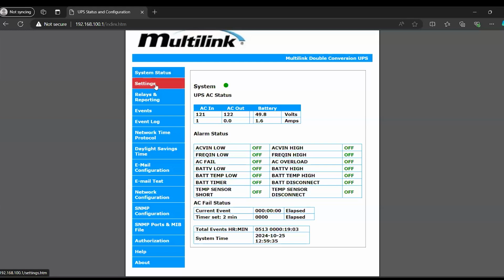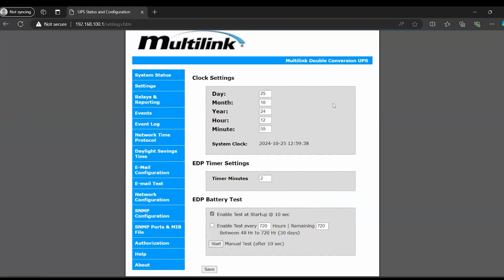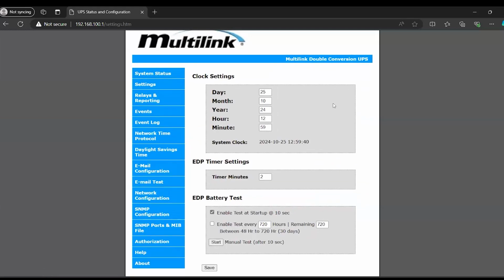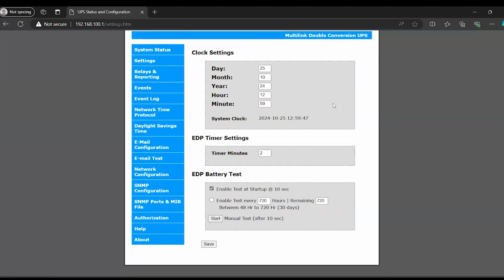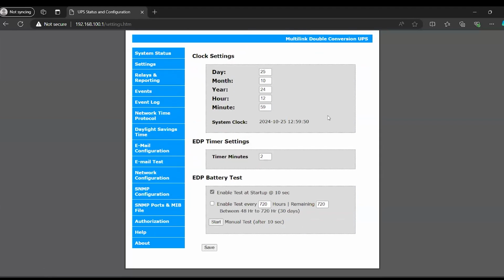After system status, we have the settings. This is where you can configure some of the settings inside of the embedded web page. This is where you can modify the internal clock of the unit. It's where you can set your timer for the EDP 2000 itself. And this is also where you can enable a self battery test. With this self battery test, it's going to automatically enter into inverter mode and start drawing power from your battery string, just to ensure that your battery string is healthy if and when you do need to use it.